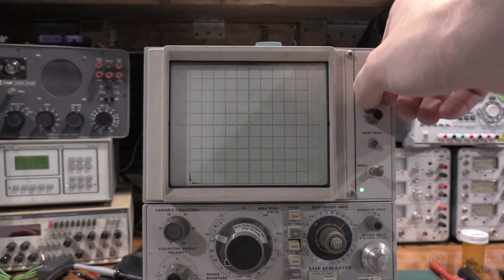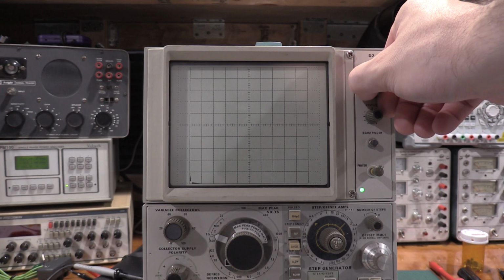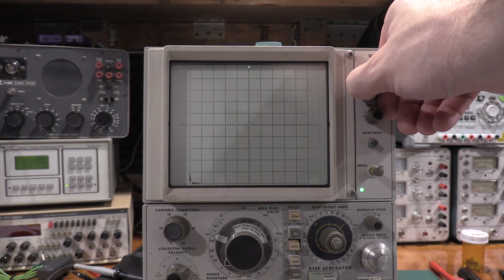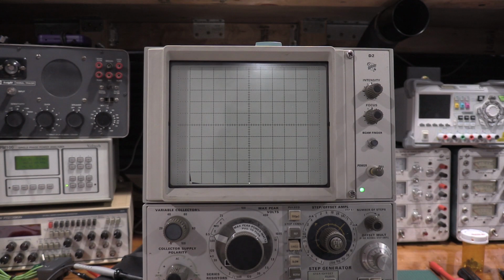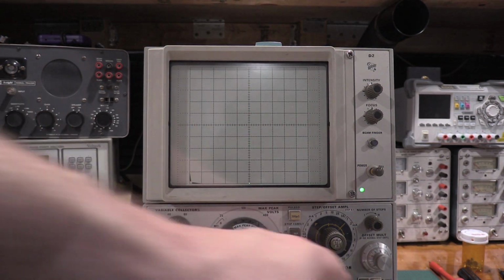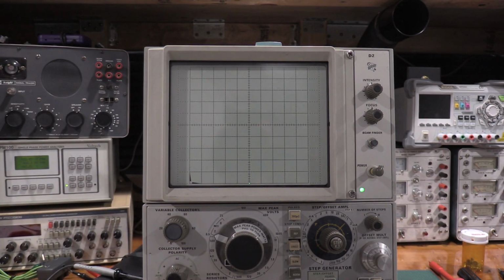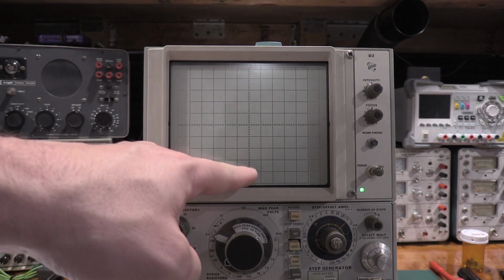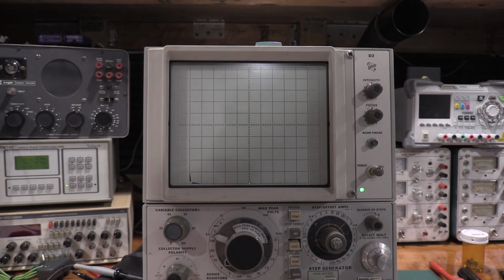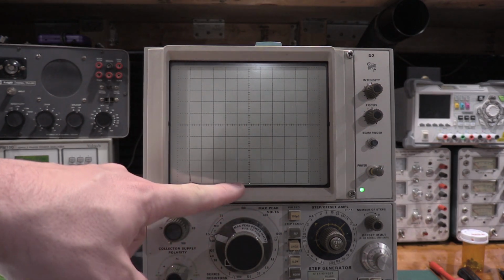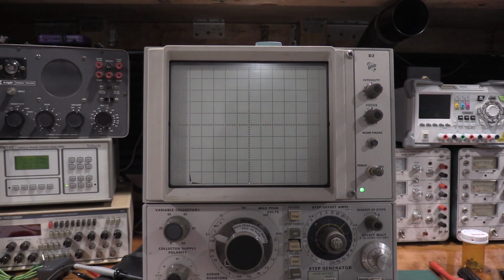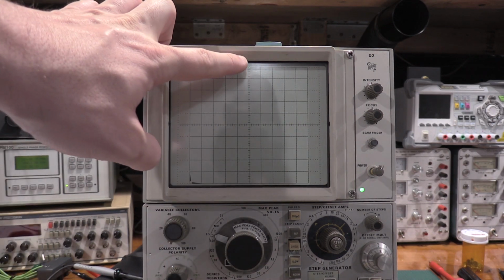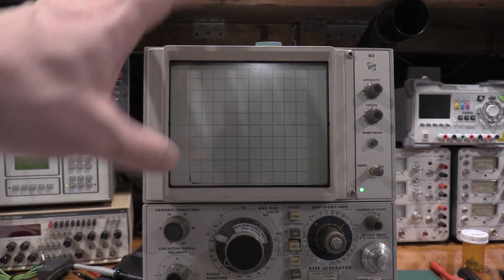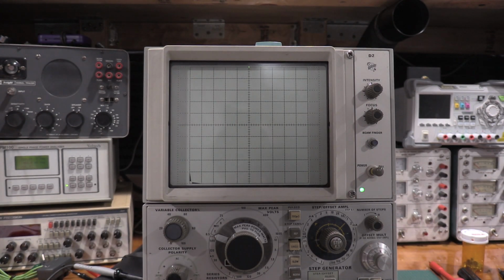Okay, so that adjustment took a few tries to get it right, but essentially what they're looking for is with 4 volts aiding as measured by the meter, which mine is saying 4.001 and 5, it's kind of bouncing. When the output's turned off, the spot should be at the bottom center. When the output's turned on, the spot should be at the top center. It just bounces back and forth, so that lines up the vertical gain.